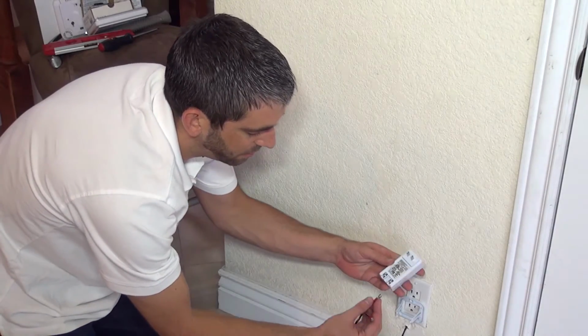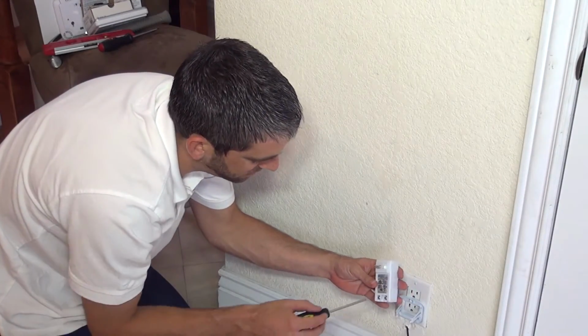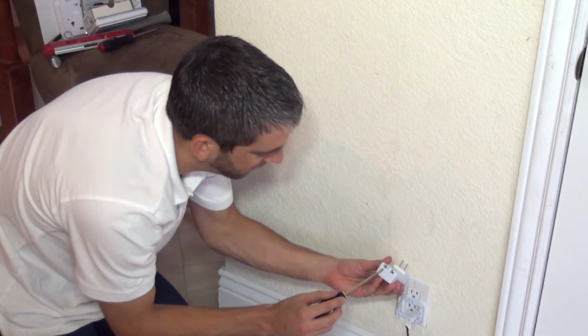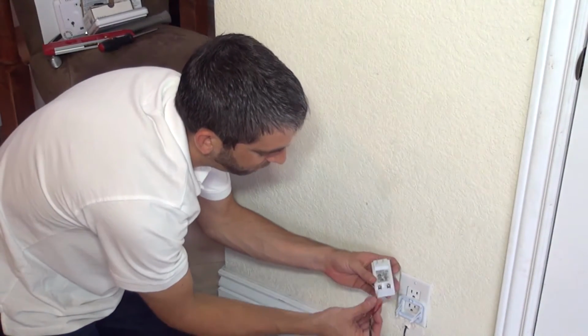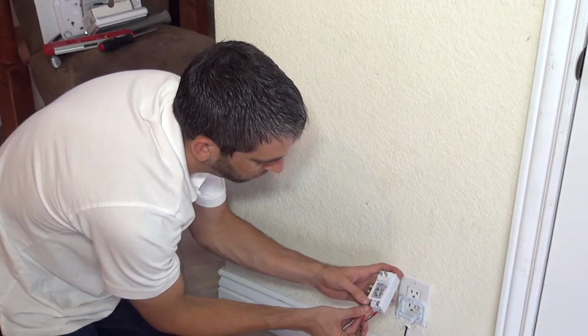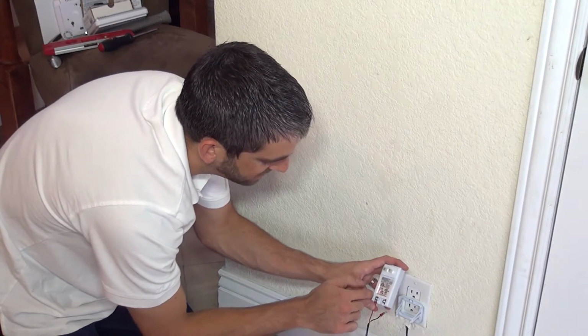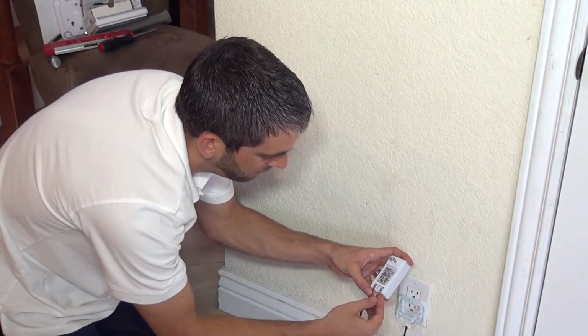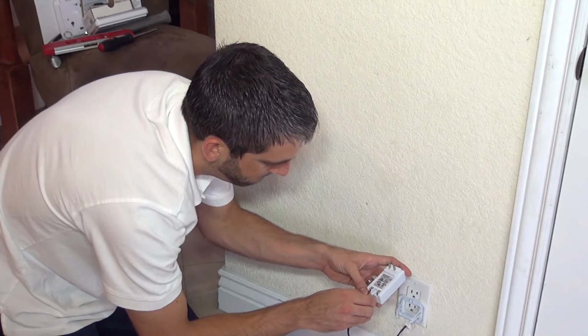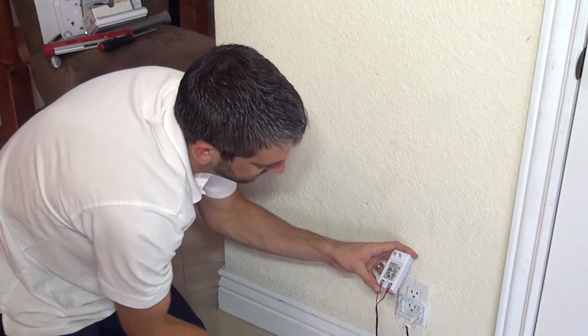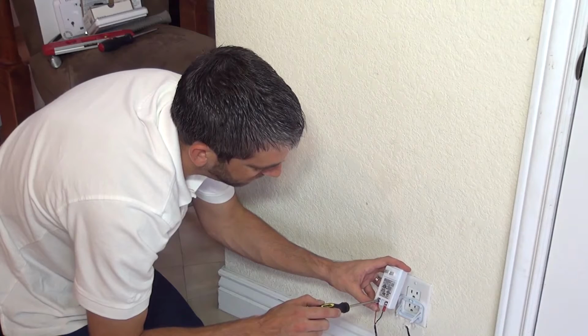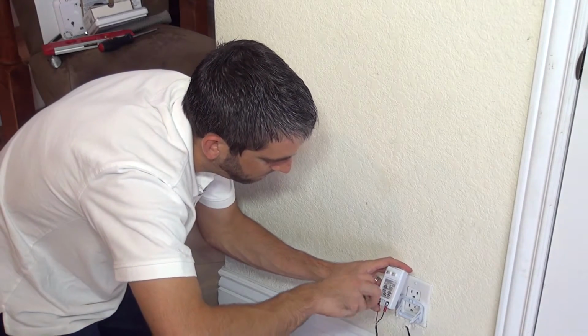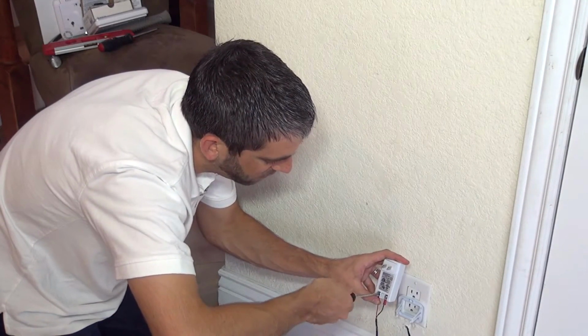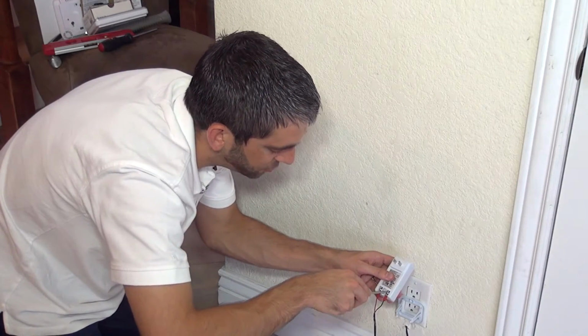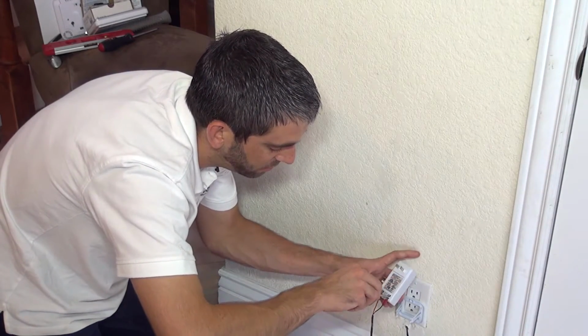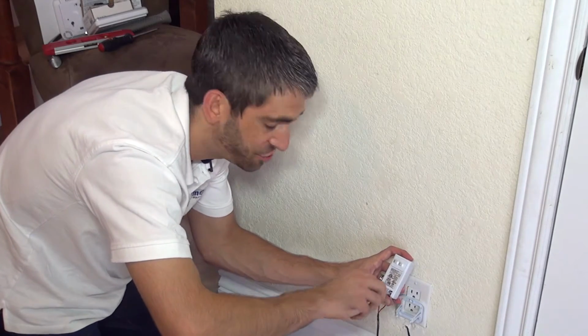In our case we use spade connectors. We've already loosened these screw terminals so there's a gap, and we just fit the spade terminal under the screw - red to positive, black to negative - and screw these down nice and tight. We don't want this to ever come undone, or we'll have AC loss issues and the system would lose complete power once the battery drained.